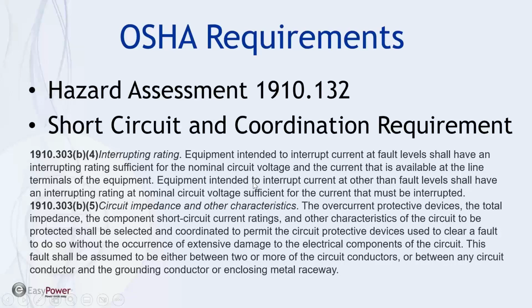Nominal voltage 208, 240, 480, 600 volt class, depending on what it is, but most of the time it'll have a specific 120/240 or 277/480 kind of thing. So the nominal voltage and the current that is available at the line terminals of the equipment. That's the available fault current.